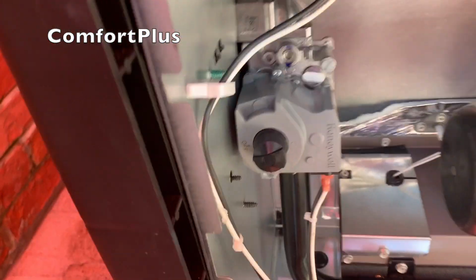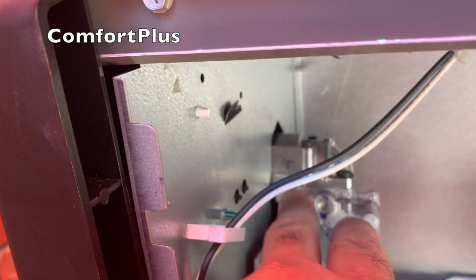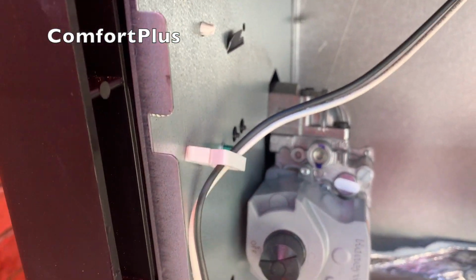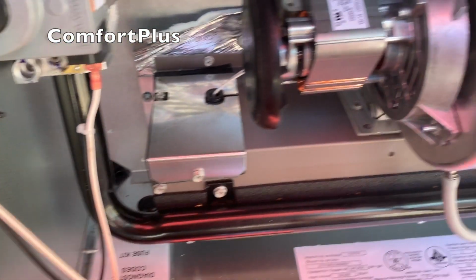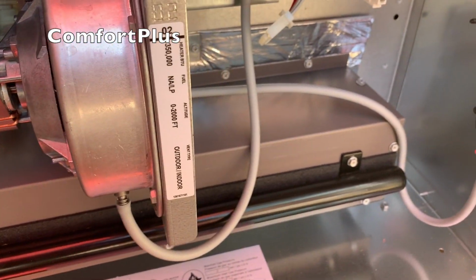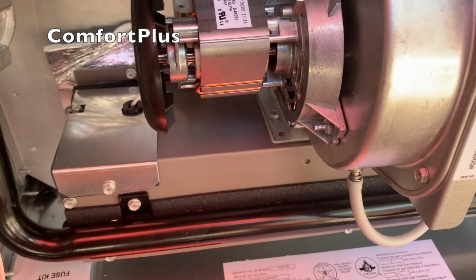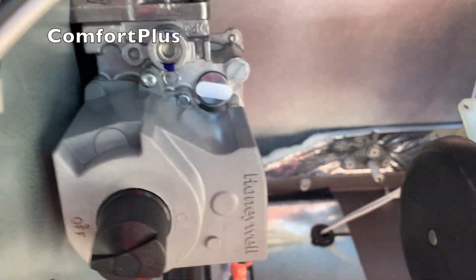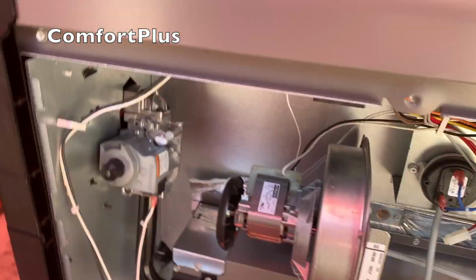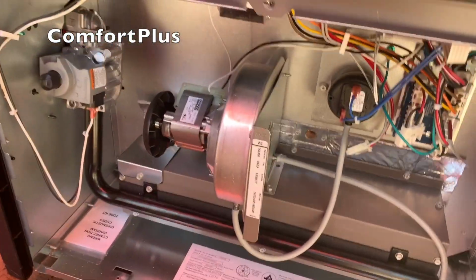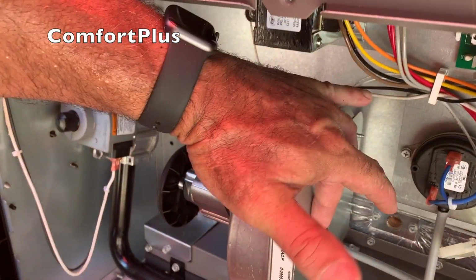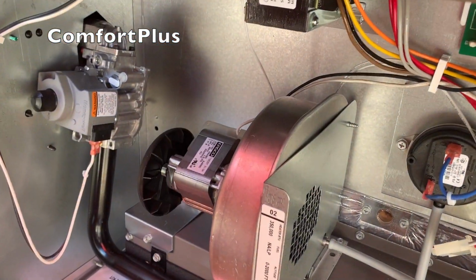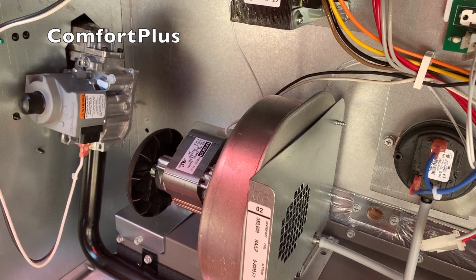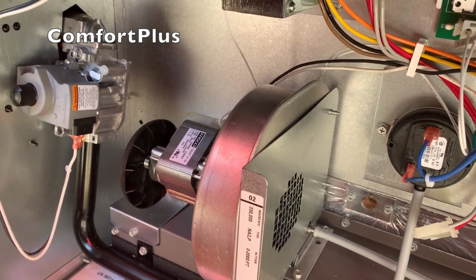Of course, as you can see, there's your gas valve. That's where I was saying it was 3/4 coming out there. Goes into the burner tray just like a normal home furnace. The difference being, I guess that's the igniter back there. The difference being, you can see your inducer fan is actually sucking air in out of the cabinet here and blowing it down into the beginning of the exchanger.